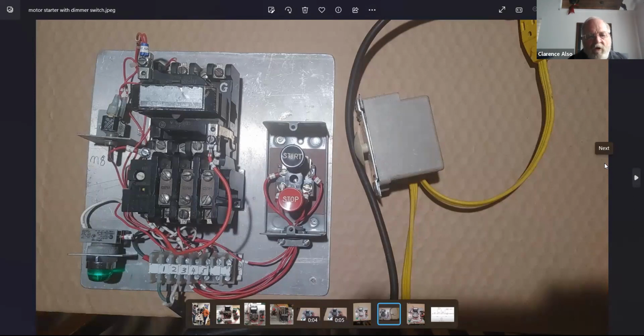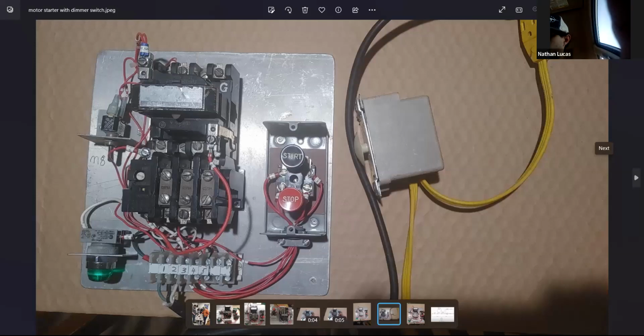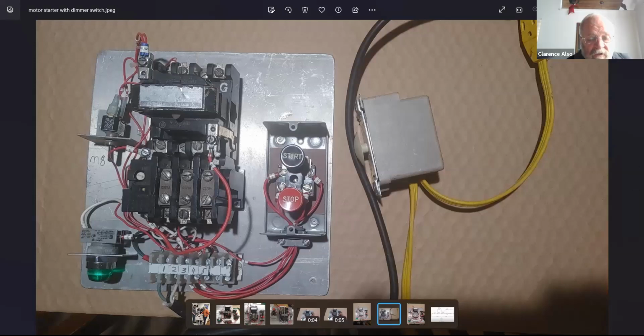And that's you troubleshooting it all the way back to where you have the problem. The problem is, when it's actually chattering, is what does it. So in this particular case, this is what caused that to chatter and that light to come on, and for that thing to not work is you had an under voltage. This is coming from your generator, maybe you got to be turning your generator voltage up or something.